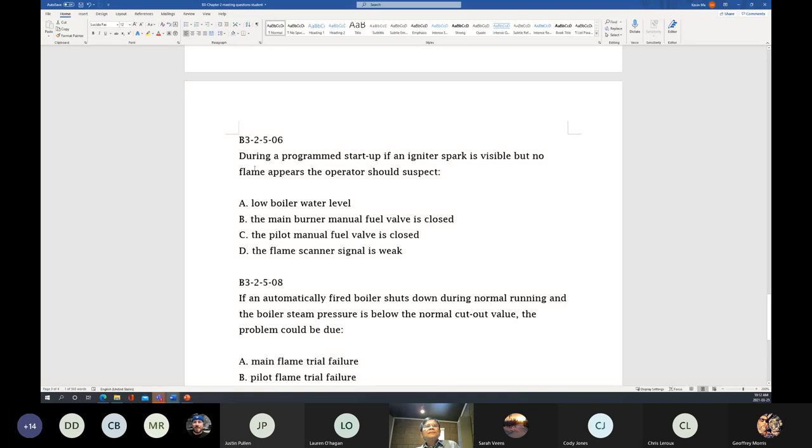Now number six. During the program, you start up and ignition spark. When you start it up, it goes through the high purge, and then you go to the back of the boiler and you see the spark, but then no flame, not even the pilot flame. What is the trouble? What is the problem? So you see spark, but no flame.